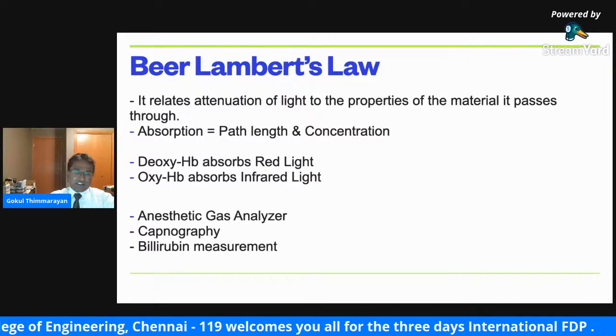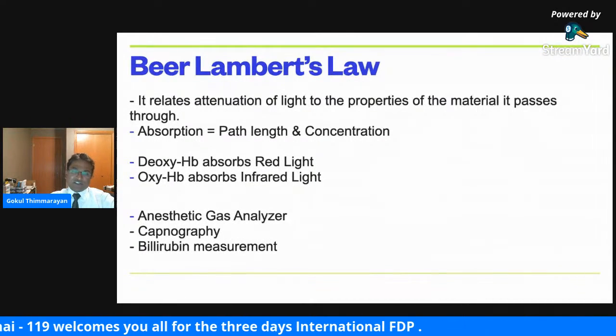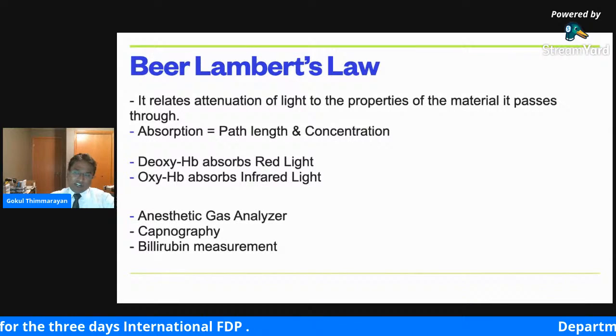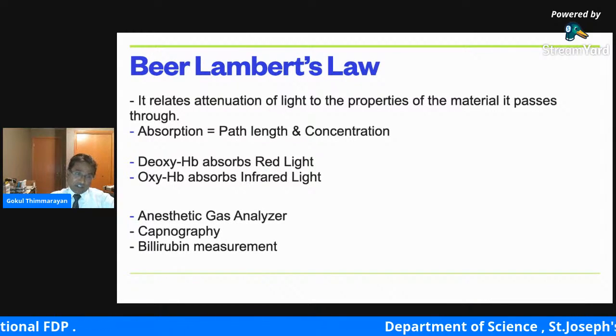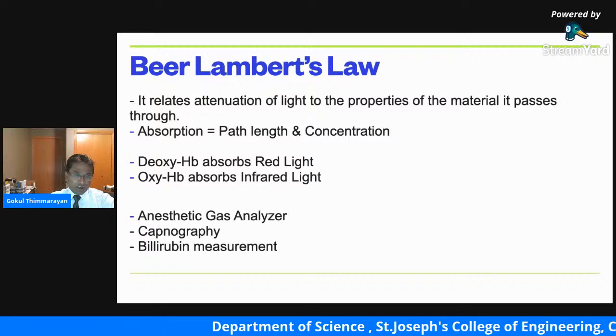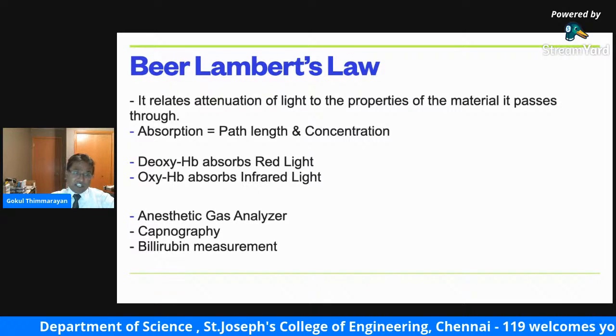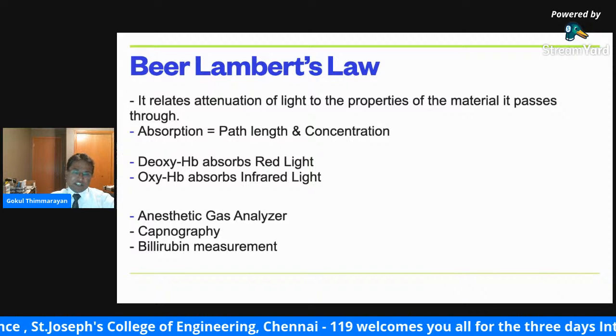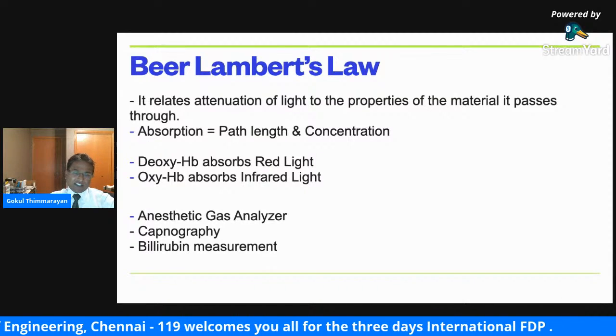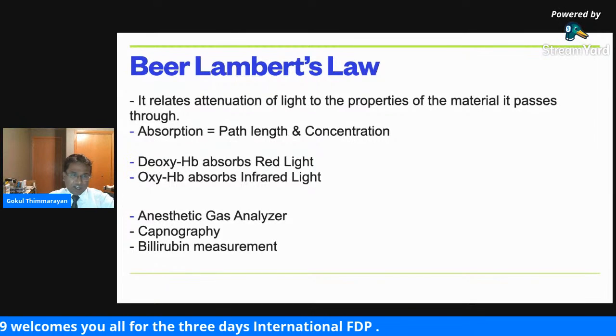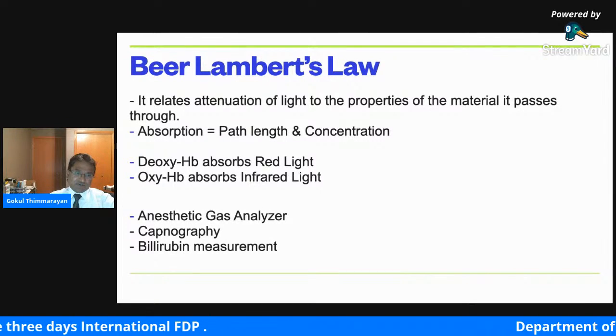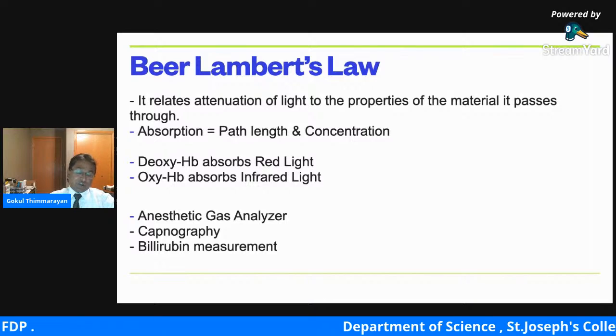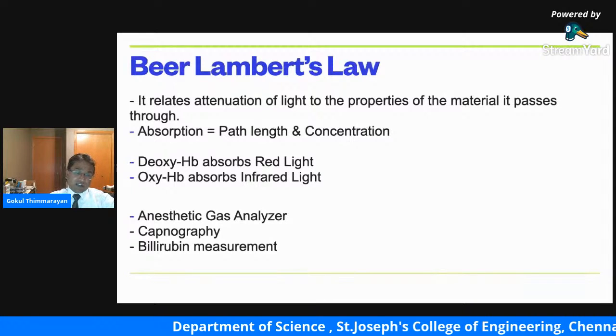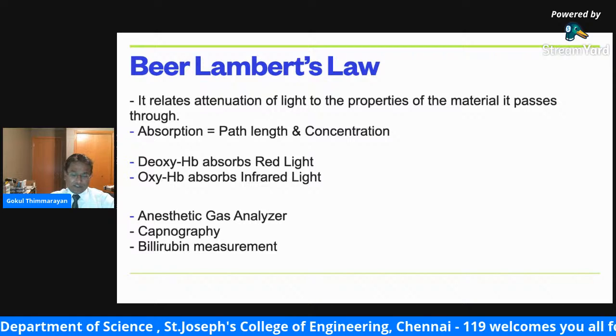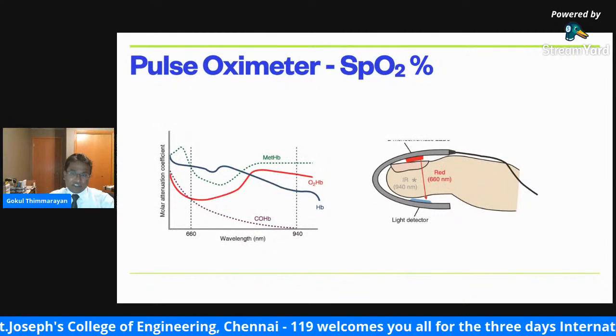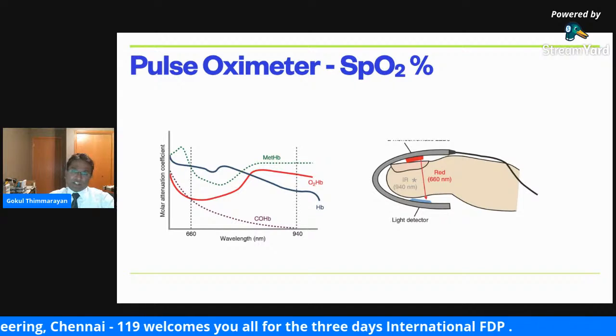In a pulse oximeter, two wavelengths of light are utilized. One is the red light and the other is the infrared light. The infrared light is absorbed by the oxygenated hemoglobin, while the red light is absorbed by the deoxygenated hemoglobin. So with the variation from the source, directed at the point of detection after absorption, the difference gives the saturation. And the same principle could be used to measure the carbon dioxide level and the bilirubin, and also in the anesthetic gas analyzer.